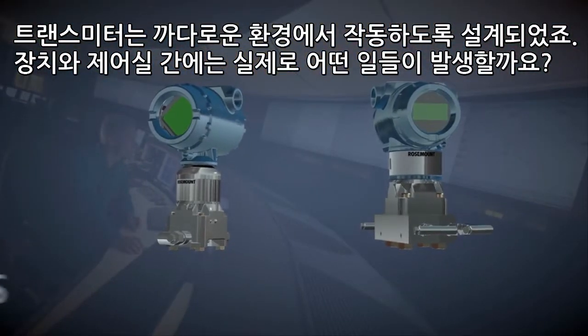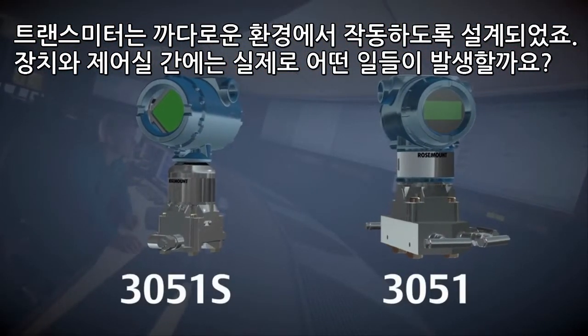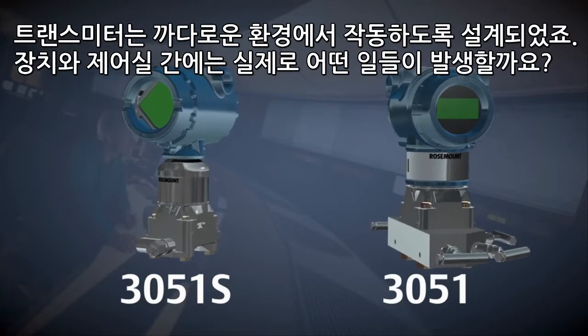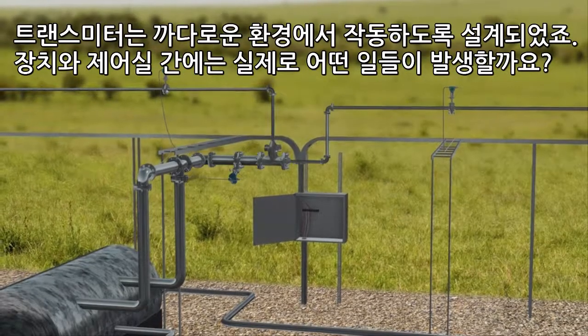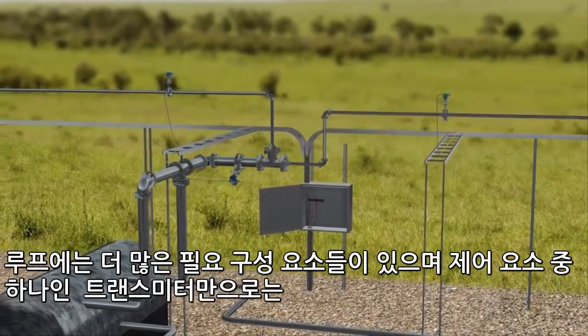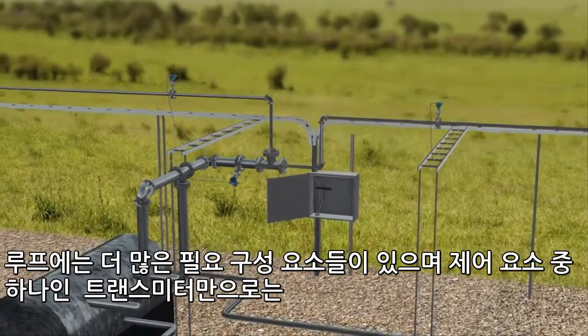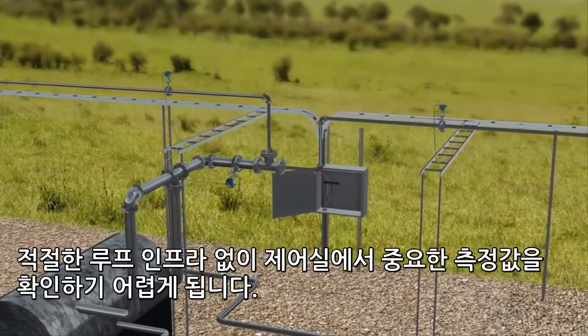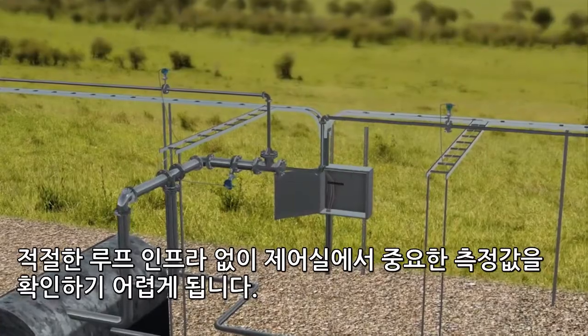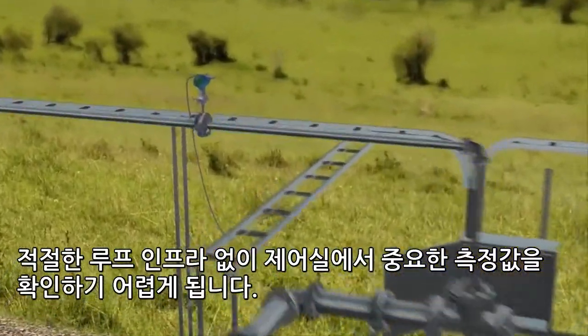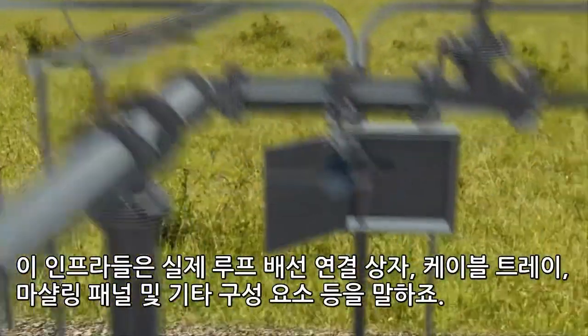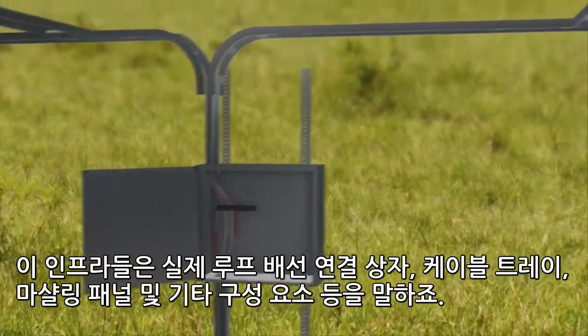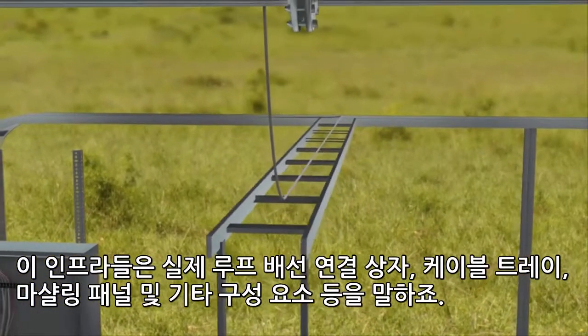Transmitters are designed to work in the harshest environments. But what happens between the devices and the control room? There is more to your loop than just your transmitters and control elements. The critical measurements that you rely on cannot be sent back to your control room without the proper loop infrastructure that includes the actual loop wiring, junction boxes, cable trays, marshalling panels, and other components.